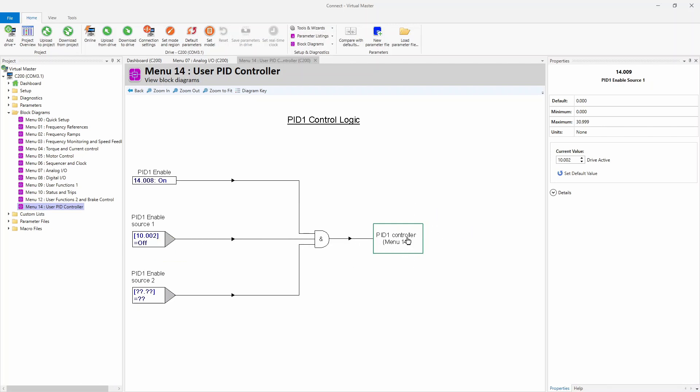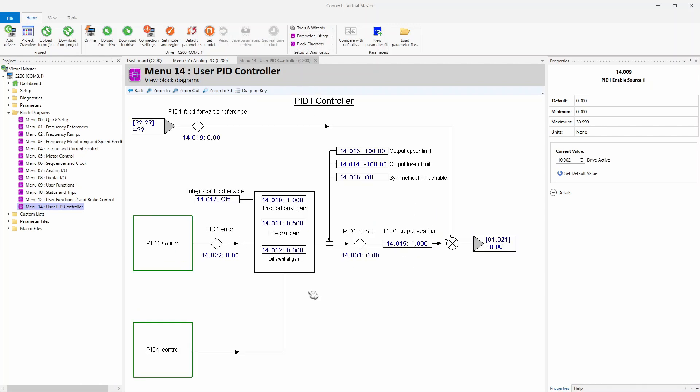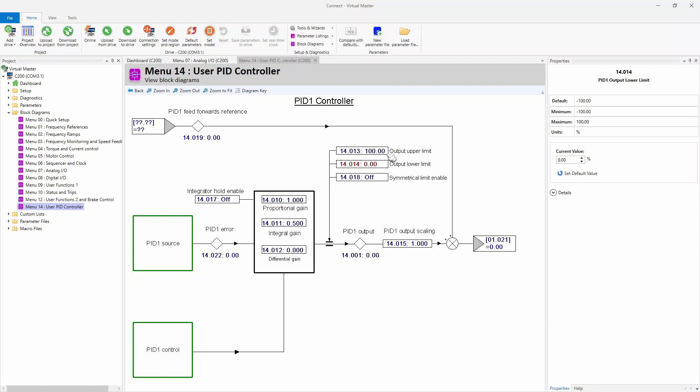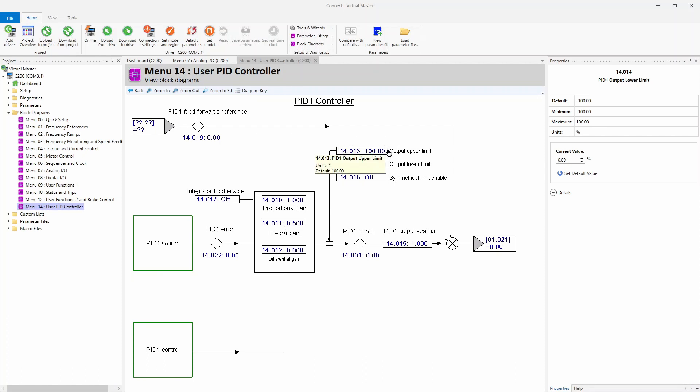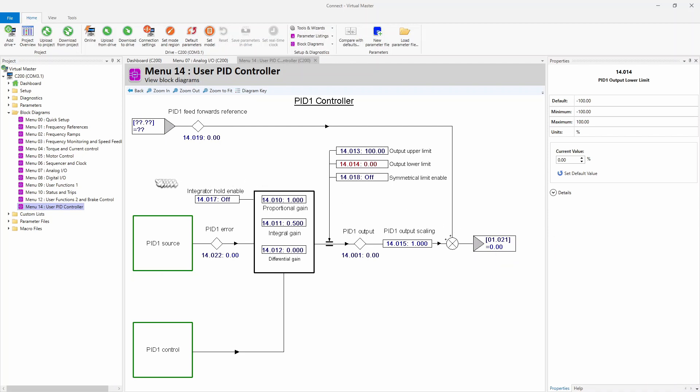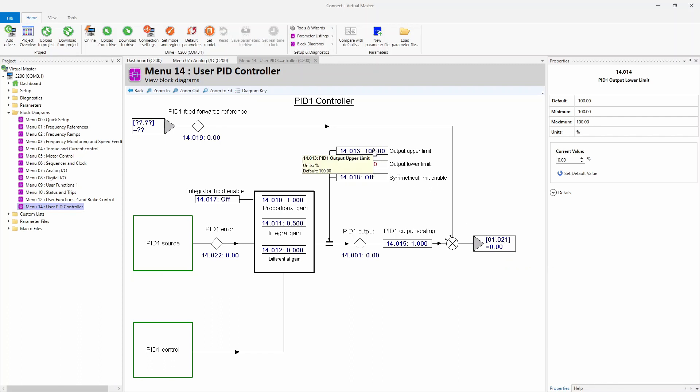If you come back here, we have everything pretty much set up. We did talk about setting the lower clamp to zero. Now you're going to notice that this says 100 here. This is actually in percentage. And in the earlier part of the video, I talked about saying 60 hertz. No, you wouldn't do that, because the way the PID works is it auto scales everything based on the parameter you're sending it to. So this parameter right here, this is parameter 121, which is a preset speed reference. If I come over to that parameter and looked at it, it would say its maximum value is 60 hertz, because the rest of the drive is set up to 60 hertz. So 100% here would output 60 hertz here automatically. So it's just a percentage of whatever this full scale is.